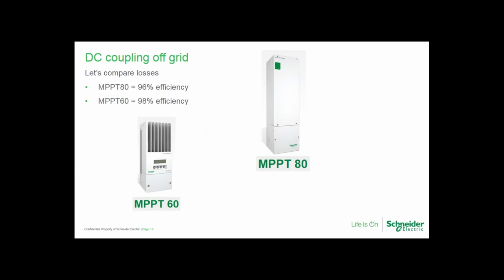Here we can see efficiencies for MPPT 60 and MPPT 80. Clearly, if you are DC coupling, then you're getting better efficiency for those loads that are possibly occurring during non-solar hours. In other words, you're storing that energy for use at a later time.